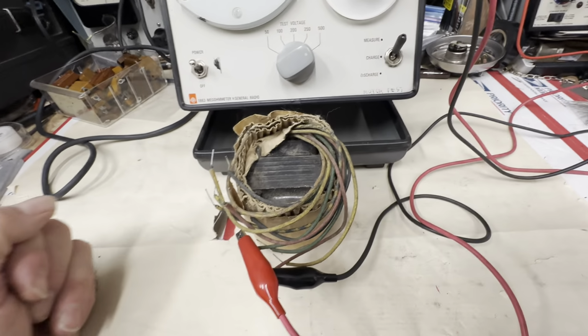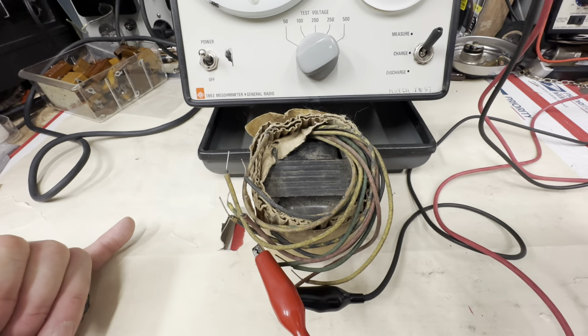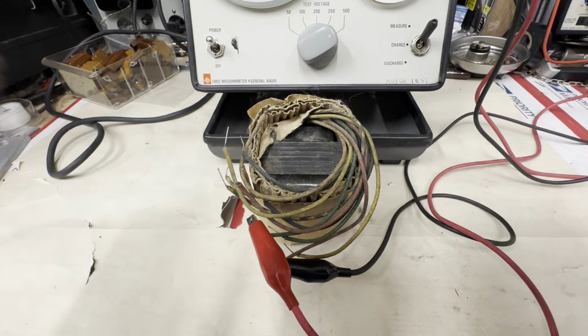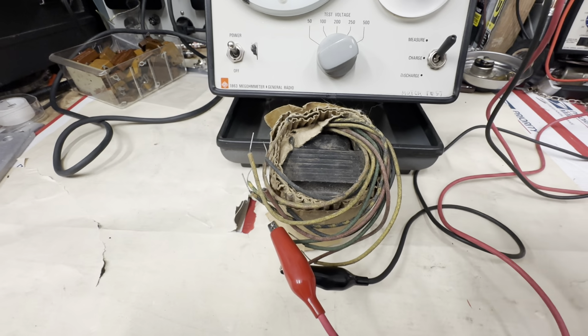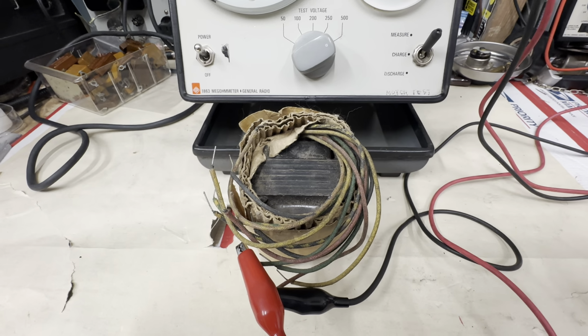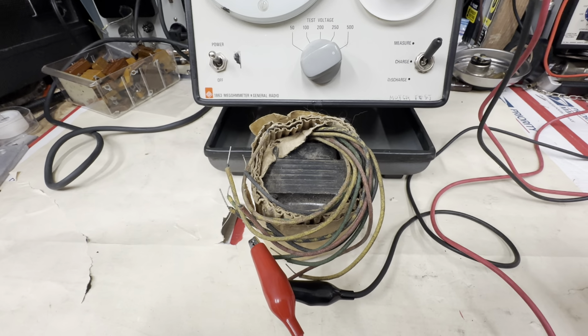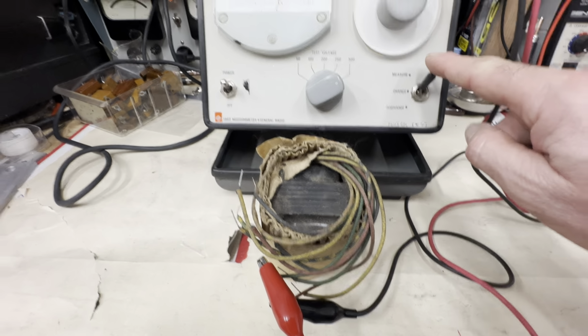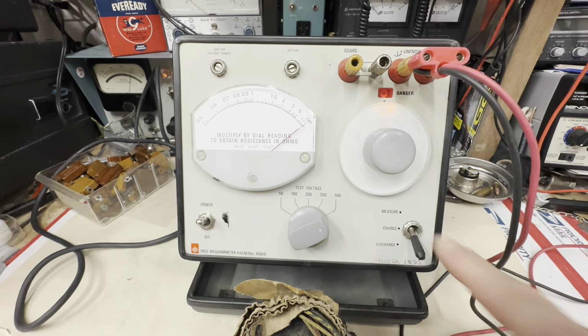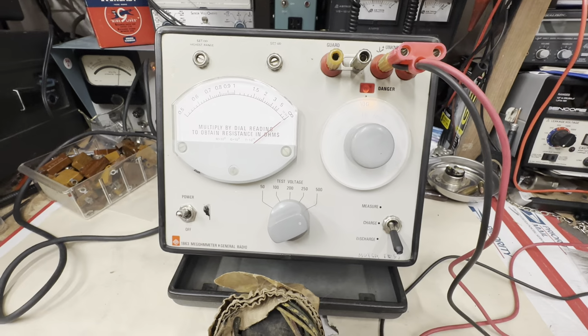We're going to go ahead and stop the test here. If we're going to do this exhaustively, we would test between all of the different windings to ground, but this is a good check right here. This is what you want to do before you take something like this and put it into service. Okay, we'll discharge that. Safety first.